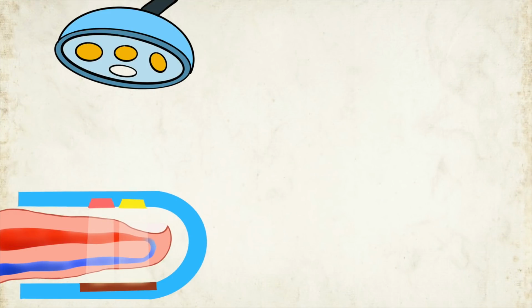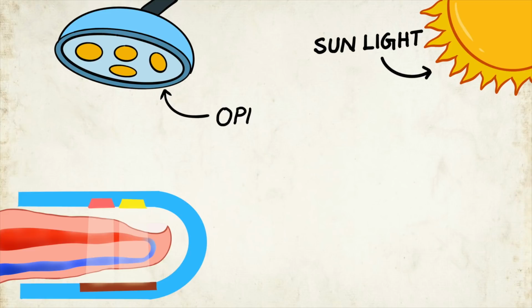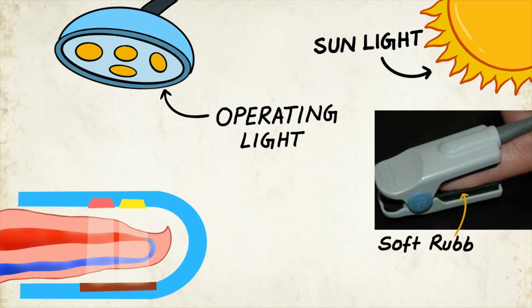Now let's see what the effects of bright light are. Bright light such as sunlight or the operating light on the probe may interfere with the light detector and cause inaccuracy. But the probe has soft rubber to shield it from the light, so be careful with the positioning of the probe. It does not have to be covered, just avoid bright light. Otherwise you might get inaccurate results on your pulse oximeter.